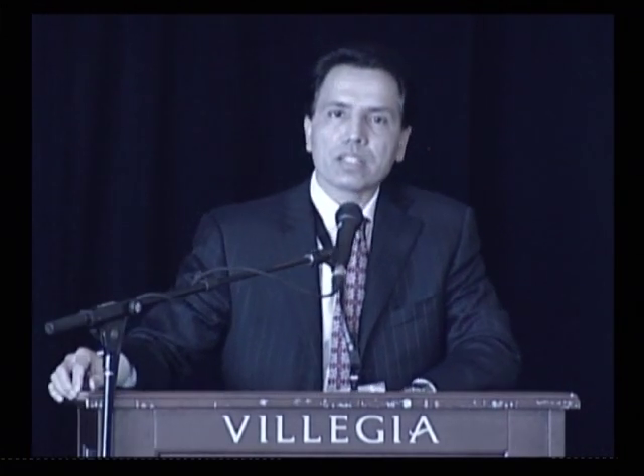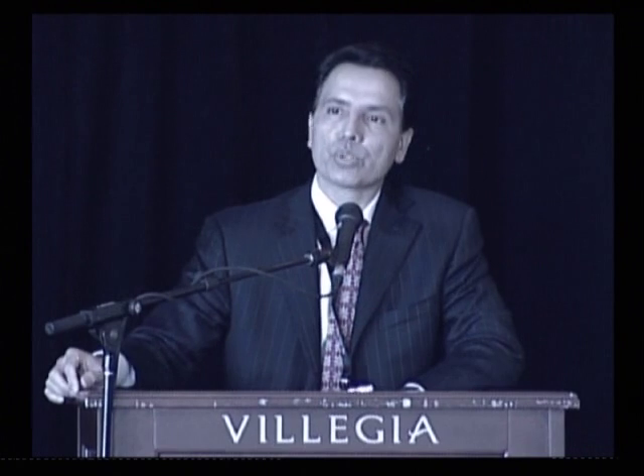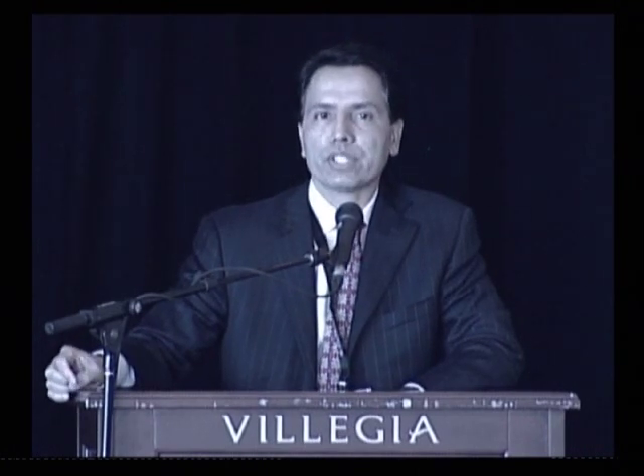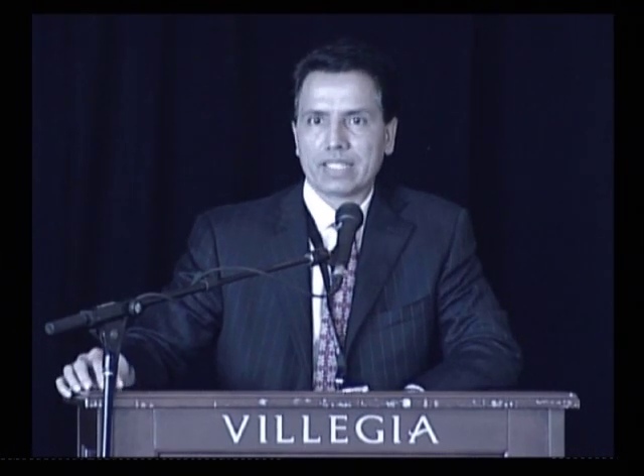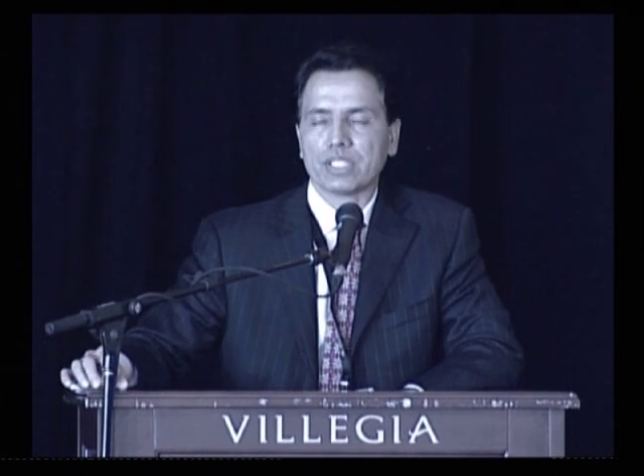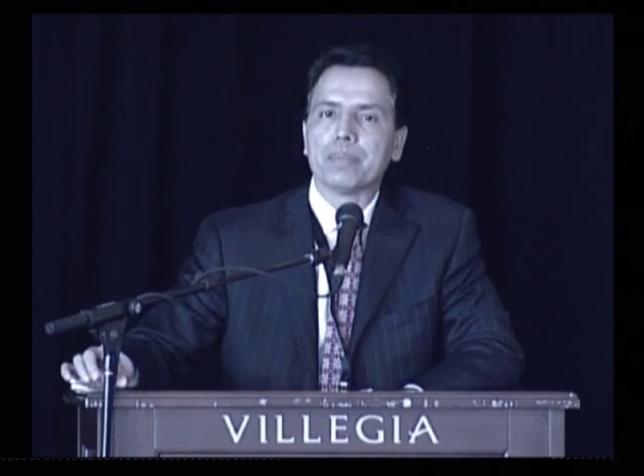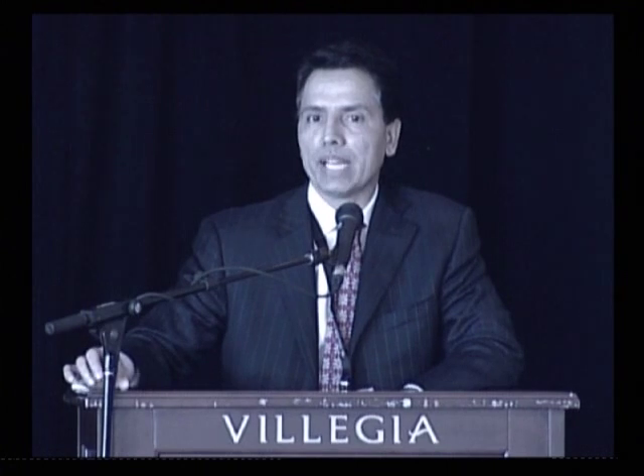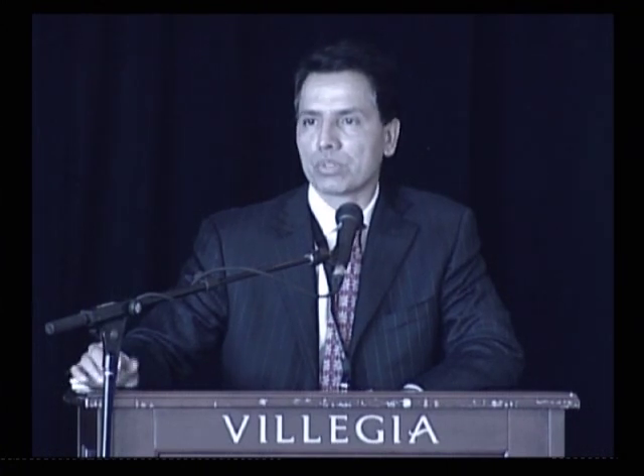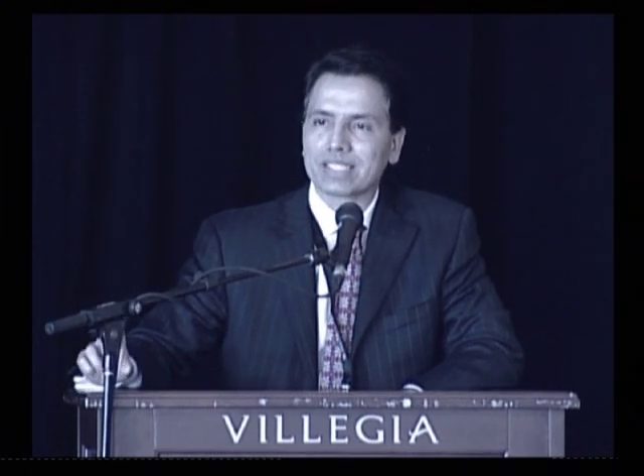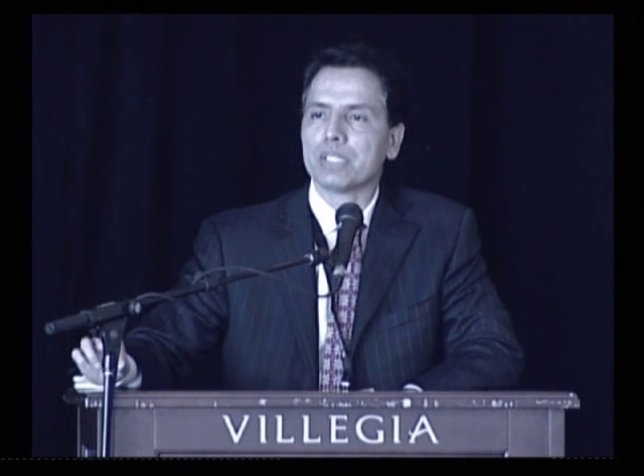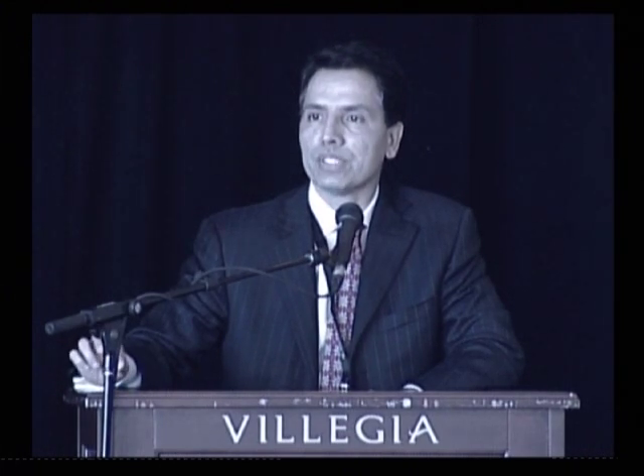Sure, Brian. So I think I showed some of that data. I think that's where the MEMS technology is really key, because when you make traditional metallic titanium sensors, there is significant drift over time, and that's been an issue. And so you had to have recalibration techniques, which require invasive procedures typically, although you can do indirect calibration without invasive procedures. So that's one reason we went to this technology, where the drift is 0.1 millimeters of mercury per year over 20 years of fatigue testing.